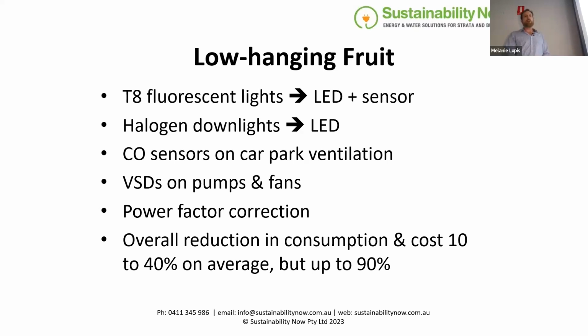CO, carbon monoxide sensors on the car park ventilation system, variable speed drives on pumps and fans. A lot of centrifugal pumps and fans don't need to run flat out all the time. You can actually achieve the same thing at a lower speed. For example, like a pool pump, if you have to achieve a certain volumetric flow, X number of litres a day filtration, you can do that at a lower speed and a lower litres per hour just for more hours, and that will save.